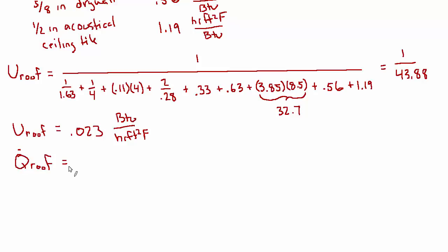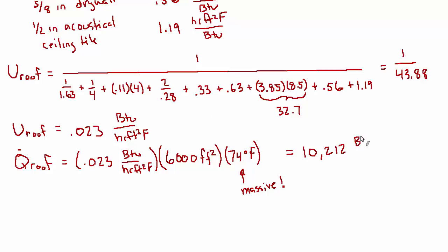Q dot roof is going to be U A delta T, where delta T is the cooling load temperature difference. So 0.023 BTU per hour foot squared degree F times the area of the roof, which is 6,000 square feet. And the CLTD that we assumed was 74 degrees Fahrenheit. And I mentioned it before, but I'll mention it again. That is a massive delta T. But it's July, and it's 4 p.m., so there's an incredible amount of solar heat load on the roof of this building.